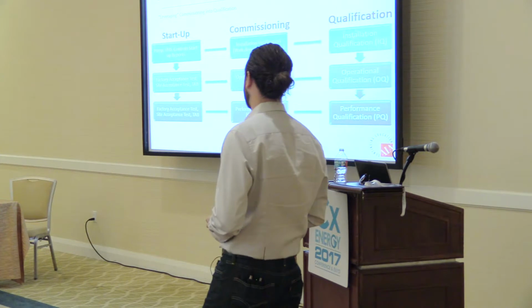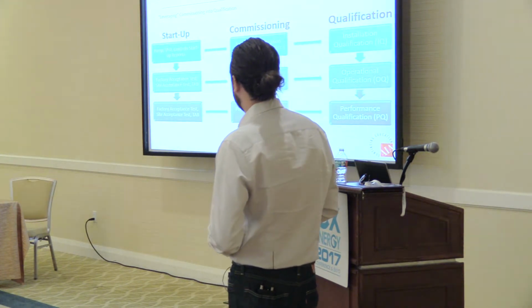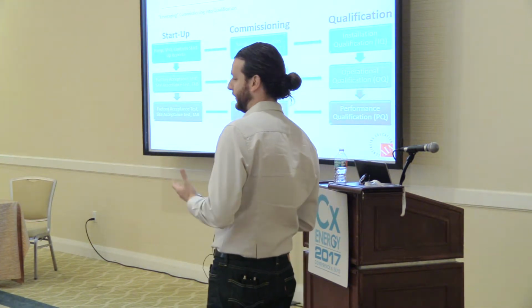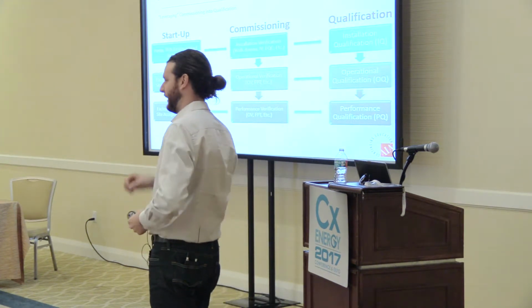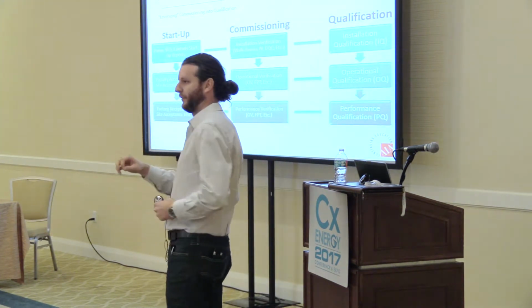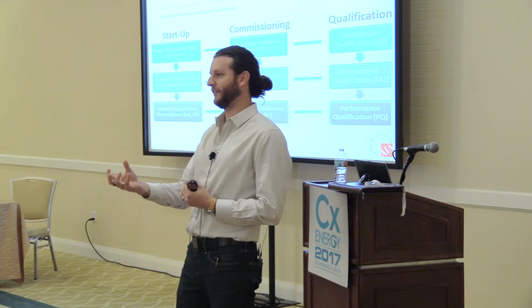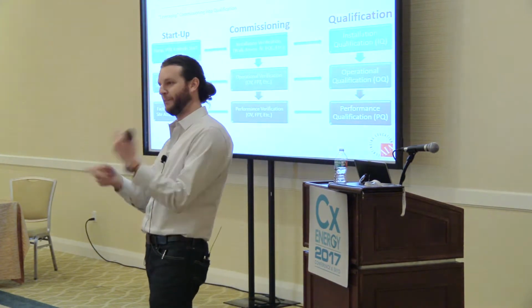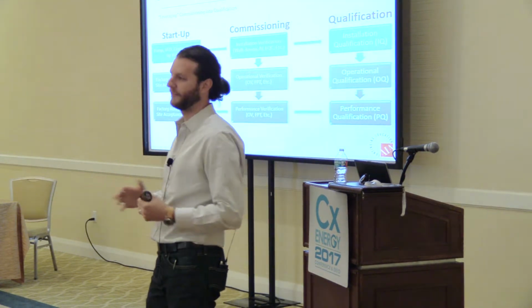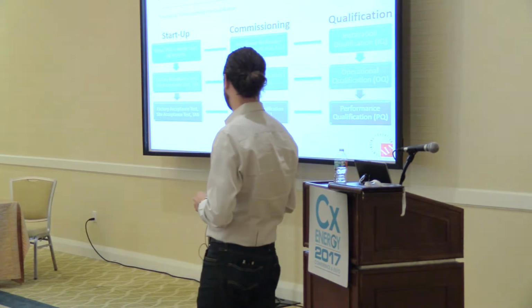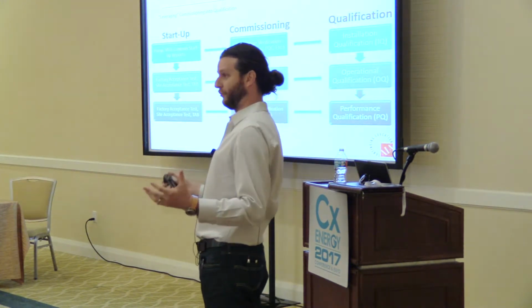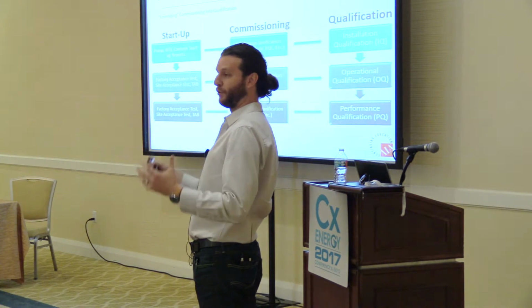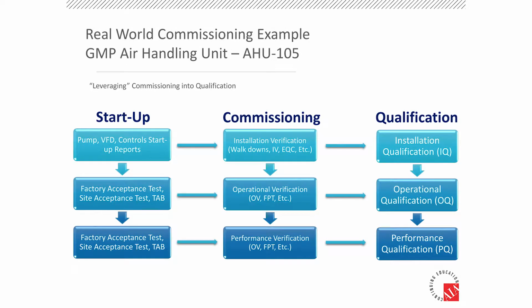It's a leveraging process where you can say, maybe my commissioning, my installation checklist where I go through and make sure that the electrical breakers are set right, the conductors to the air handling system are tightened, the fan spins the right way, there's safe access, all these things. They can take that documentation, and if it meets GDP, good documentation practices, they can leverage that into what they call qualification. And that's the next step in the process, installation qualification.